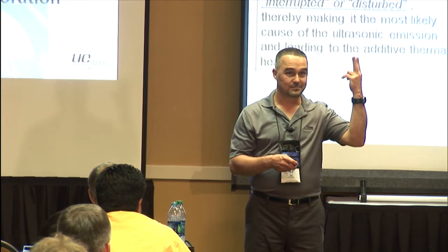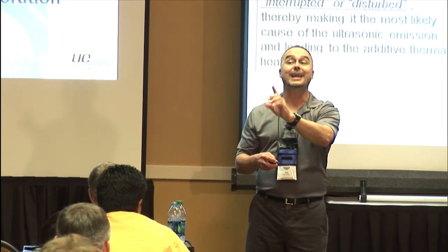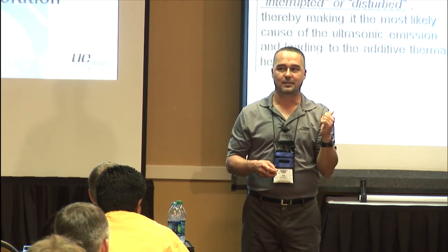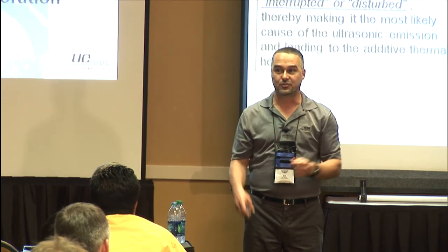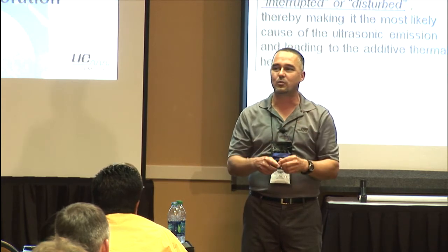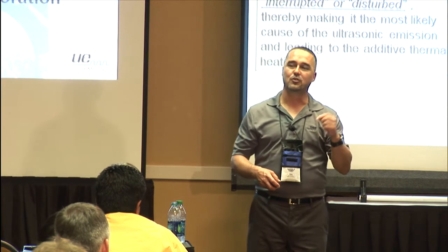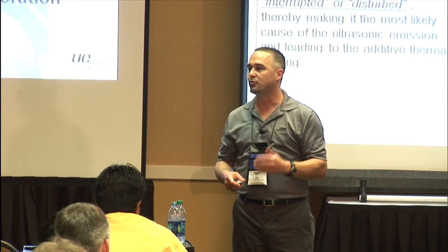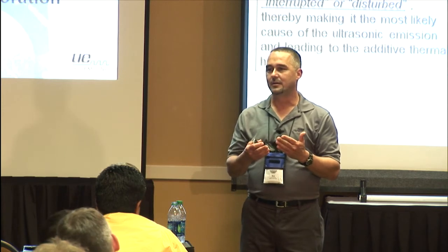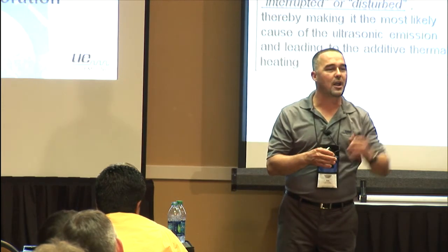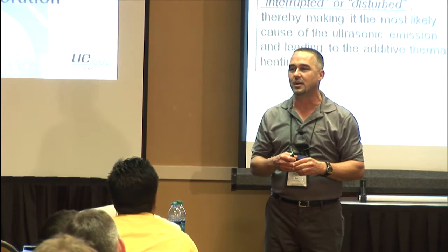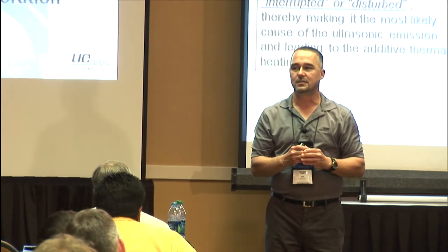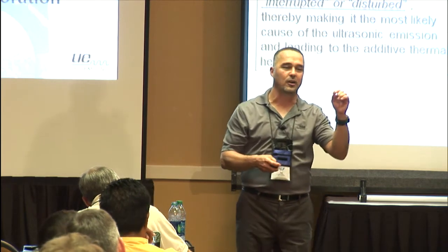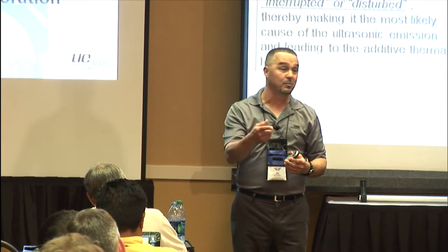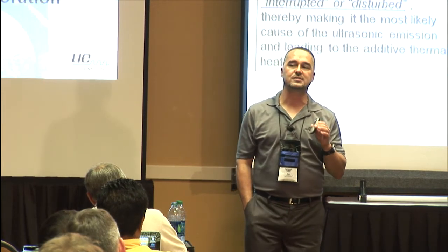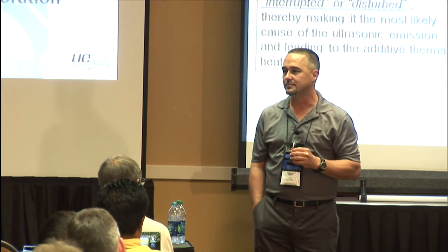What was it? Arcing. Well, not arcing yet - it could, but in this case it didn't. But it's going to create thermal energy. We saw that because the flux density is not going to be what it needs to be to do its job. It's also going to create ultrasound, which it did. It was causing these laminates to vibrate. Remember on the FFT, I said there's not 60 hertz harmonics present on this spectrum. There was a shift in the frequencies, and it's all about that vibration. Slight 30 hertz, not as pronounced as I'm used to seeing, but it led me to believe we had something mechanical.